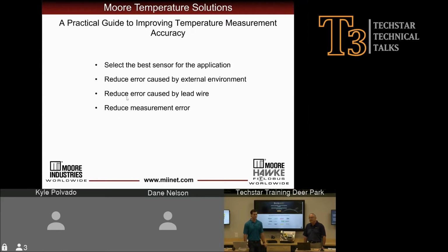So what we're going to discuss today, we're going to talk about selecting the best sensor for an application. We're going to talk about how you might reduce error caused by external environments, reduce the error that might be caused from a lead wire, for a thermocouple extension wire, RTD extension wire, and how to reduce measurement error at the measurement source, so at your transmitter. And then we'll discuss how to calibrate transmitters and sensors to each other to get a more defined temperature measurement.